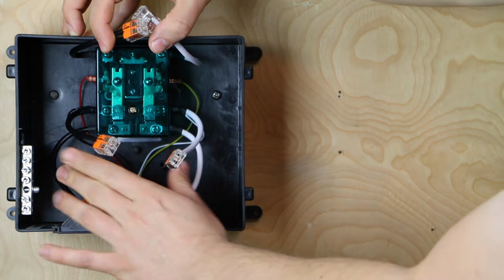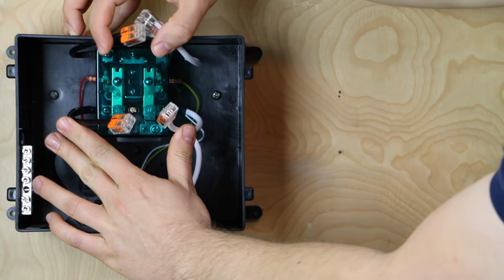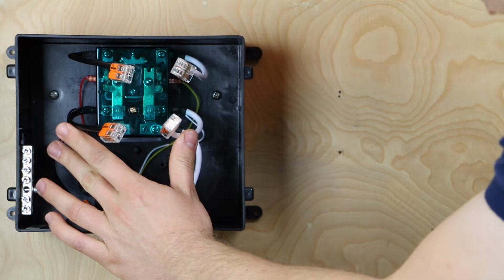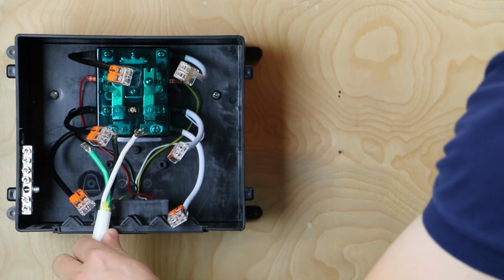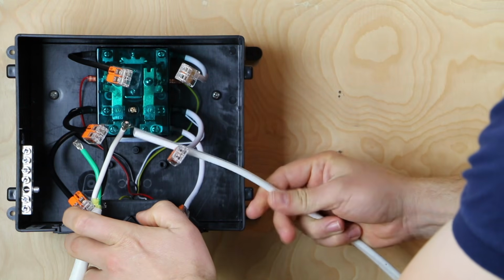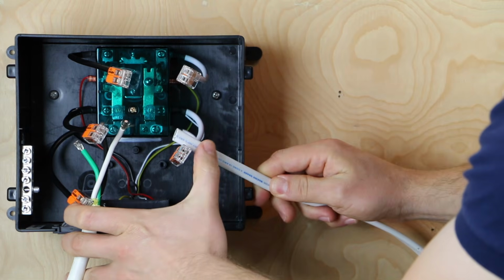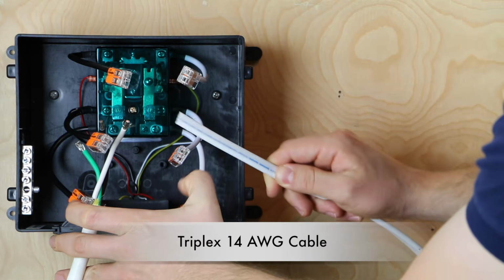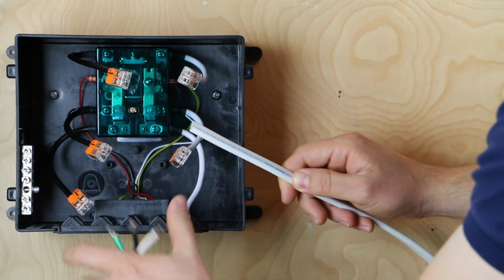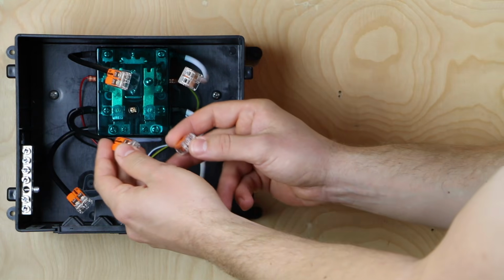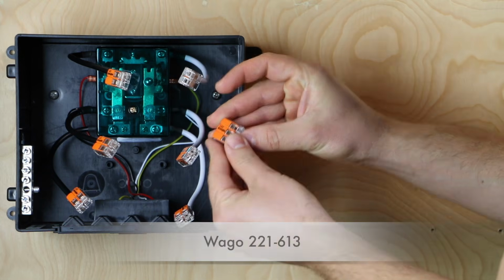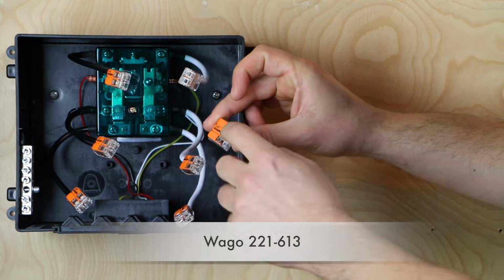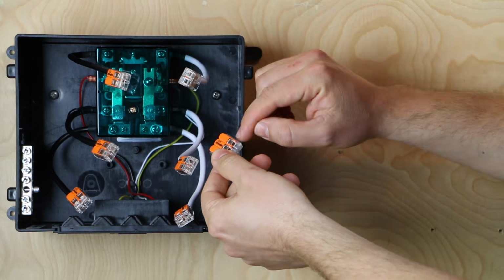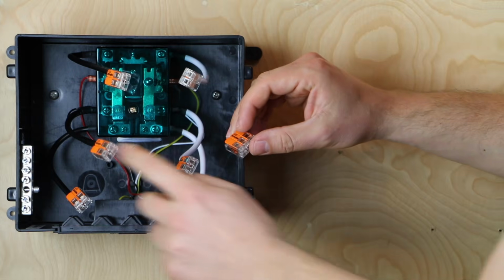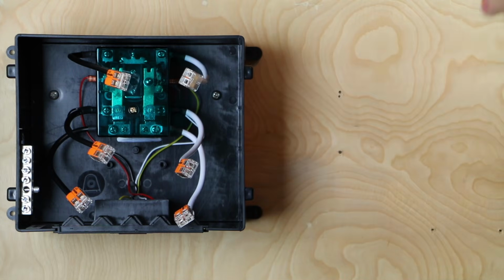To take that one step further, the power grid wires come into this middle pair, and that's where we need to send power over to our charger. So the power grid feeds that pair, and then our charger wire comes in. This is actually a 3-conductor cable, with black, white, and green inside. We're using these WAGO 221 connectors, the 2-way ones, and I've got some 3-way connectors we'll use to replace them for these two wires. That gives us an extra slot to tie in the charger hot and neutral and siphon off power at that point.